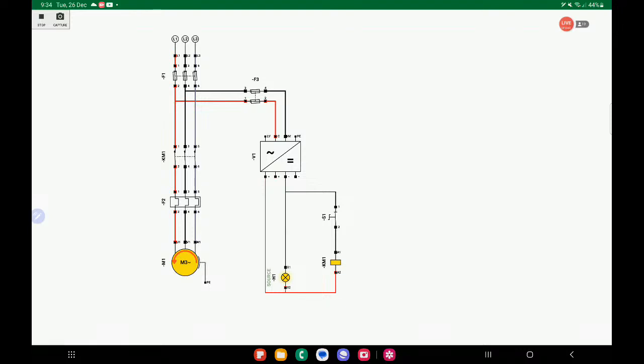So the first safety we need to put is that stopping limit switch, so that once it reaches about 30 centimeters before its home position, the electrical side should already stop. This means once this limit switch is hit, it will open the circuit. So what we need is a normally closed limit switch.